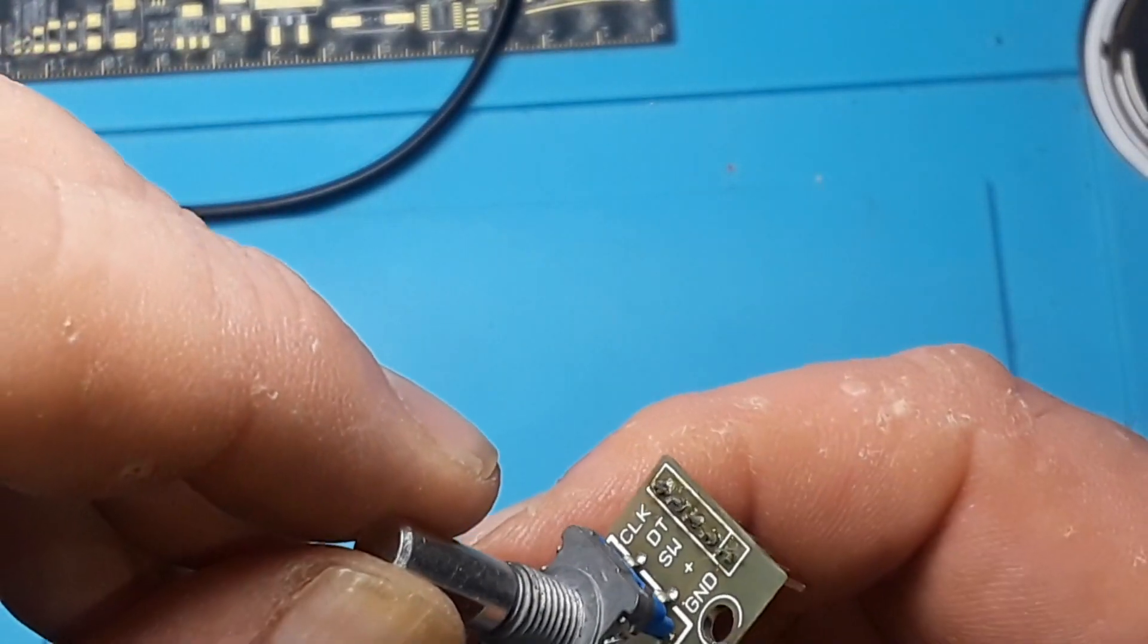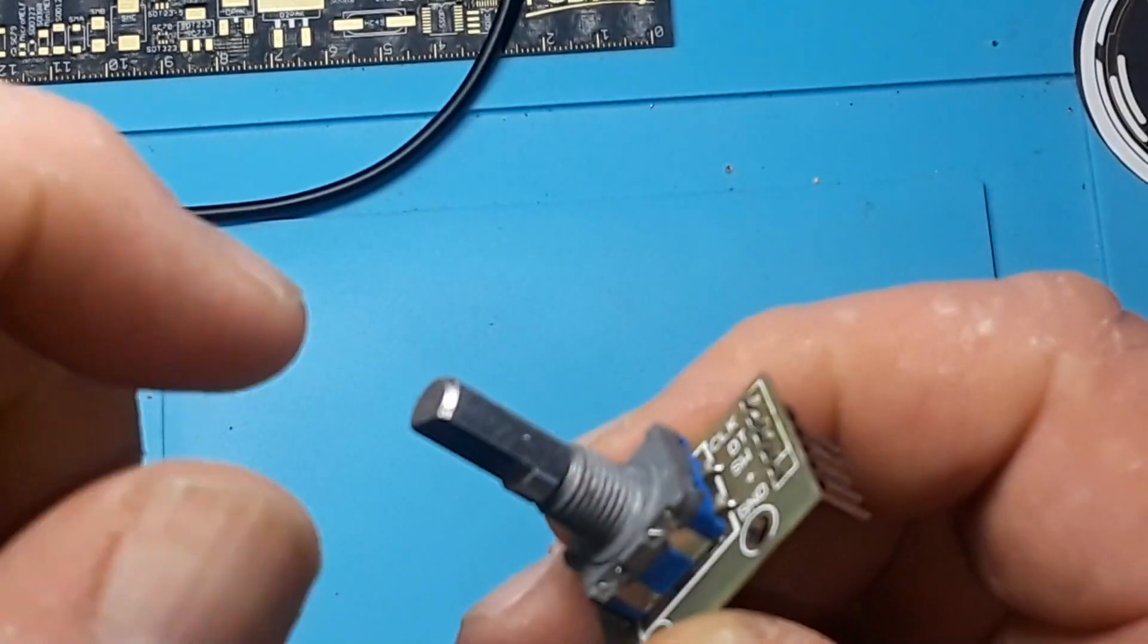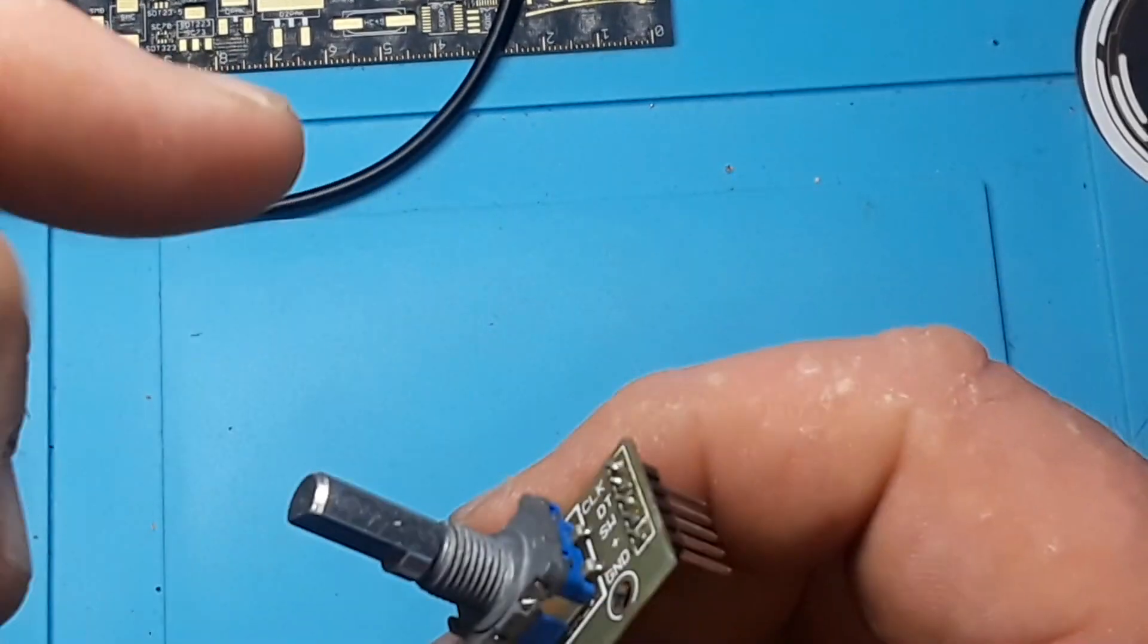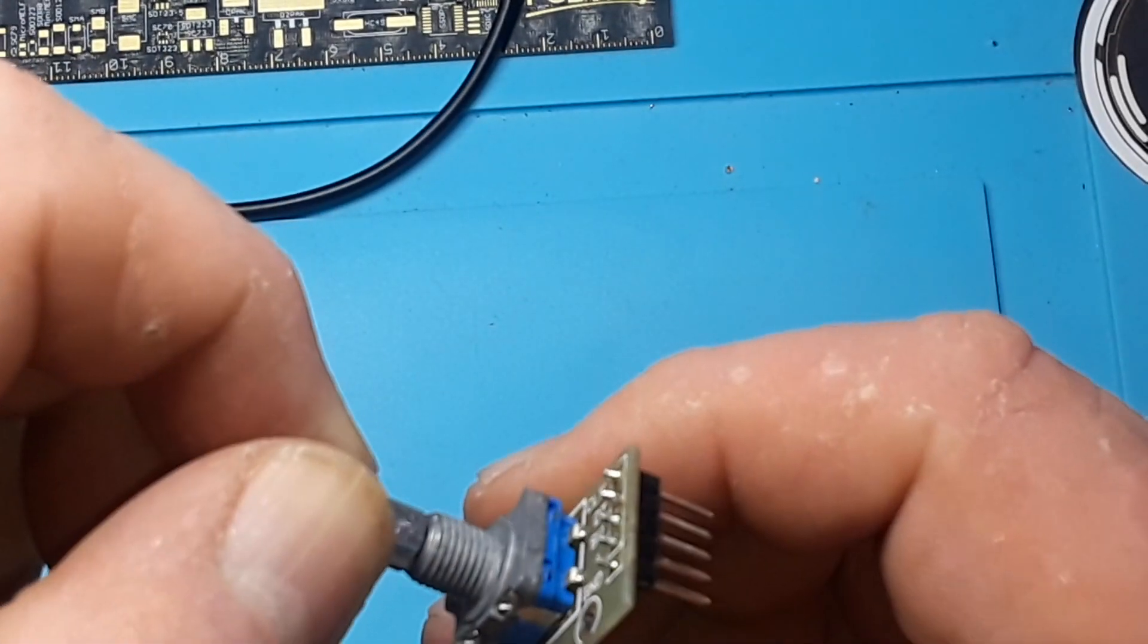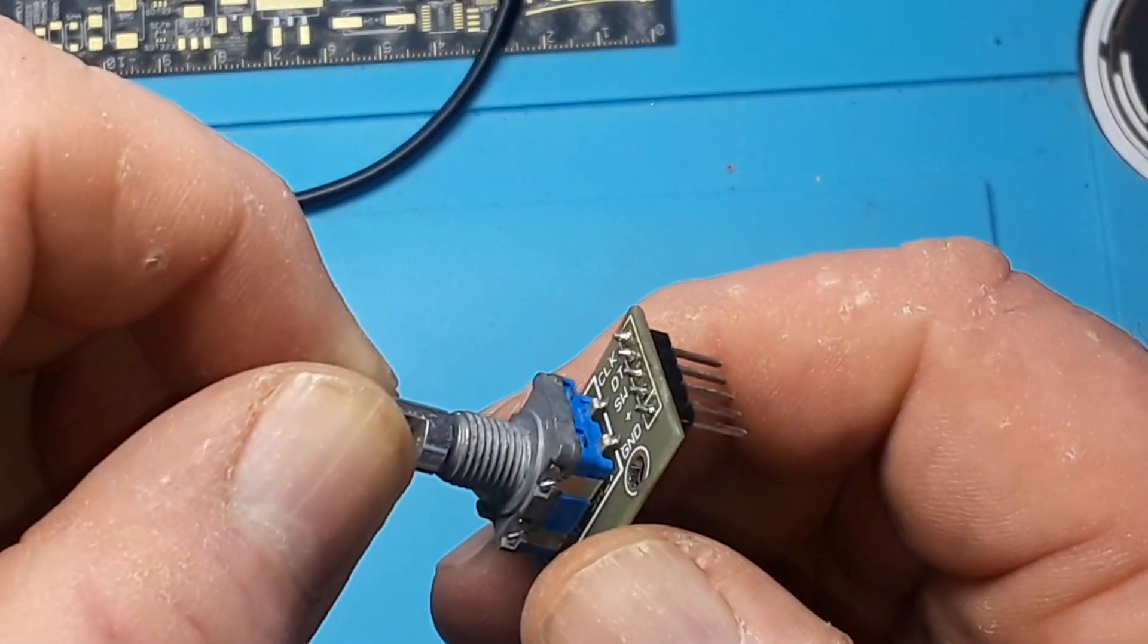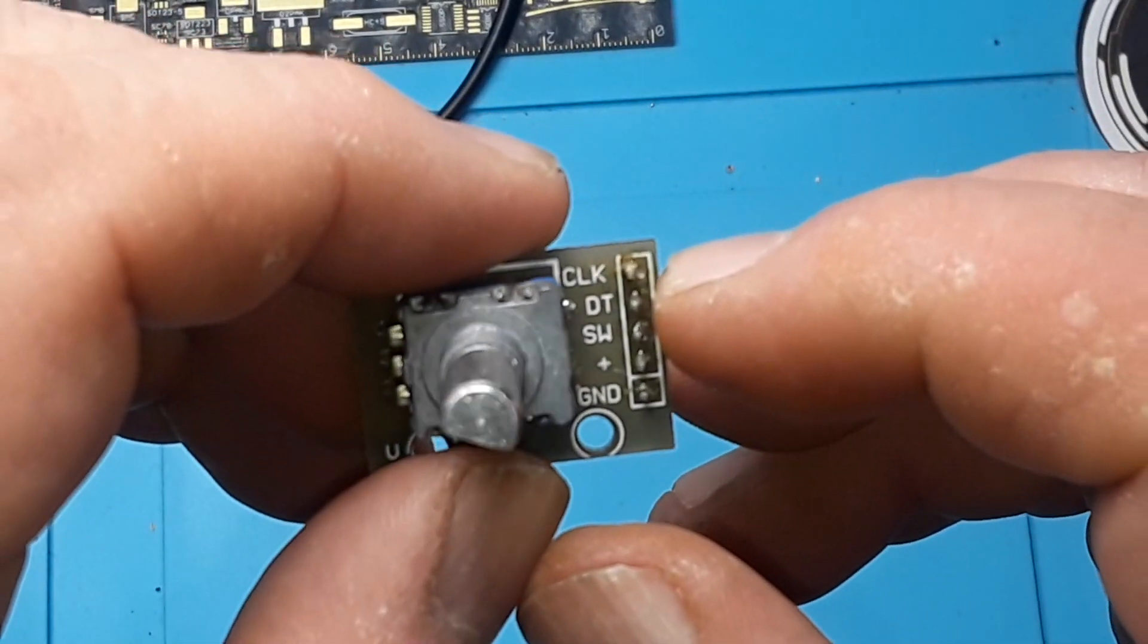There are also absolute encoders. The main difference is an absolute encoder remembers its position even when power is removed. An incremental encoder does not. And this is a mechanical—there's just a little circuit board down in there with a couple of different rings.